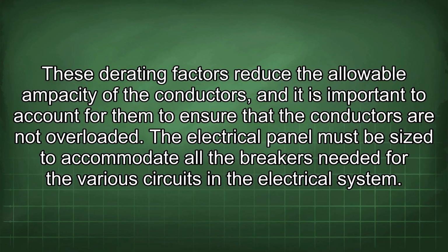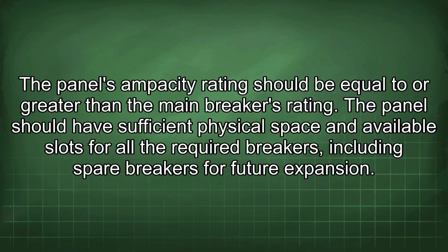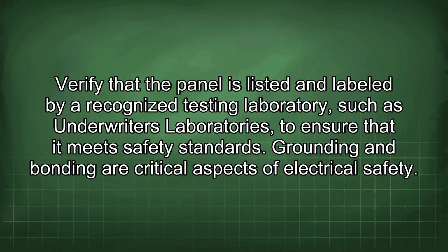The electrical panel must be sized to accommodate all the breakers needed for the various circuits in the electrical system. The panel's ampacity rating should be equal to or greater than the main breaker's rating. The panel should have sufficient physical space and available slots for all the required breakers, including spare breakers for future expansion. Verify that the panel is listed and labeled by a recognized testing laboratory, such as Underwriters Laboratories, to ensure that it meets safety standards.